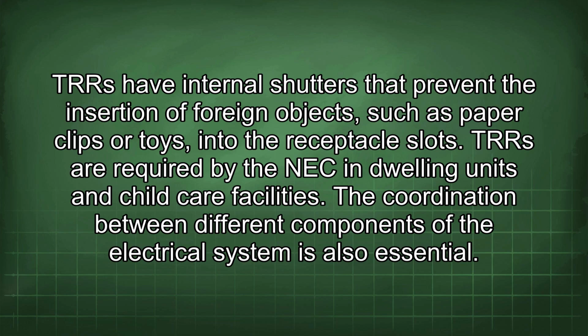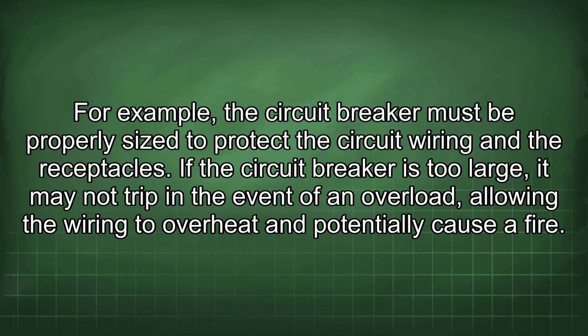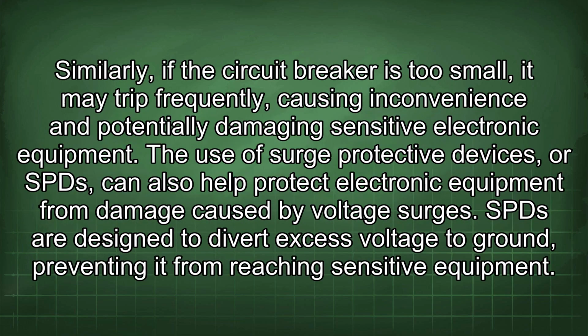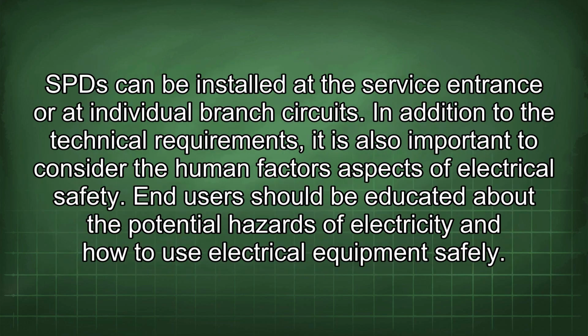The coordination between different components of the electrical system is also essential. For example, the circuit breaker must be properly sized to protect the circuit wiring and the receptacles. If the circuit breaker is too large, it may not trip in the event of an overload, allowing the wiring to overheat and potentially cause a fire. Similarly, if the circuit breaker is too small, it may trip frequently, causing inconvenience and potentially damaging sensitive electronic equipment. The use of surge protective devices, or SPDs, can also help protect electronic equipment from damage caused by voltage surges. SPDs are designed to divert excess voltage to ground, preventing it from reaching sensitive equipment. SPDs can be installed at the service entrance or at individual branch circuits.